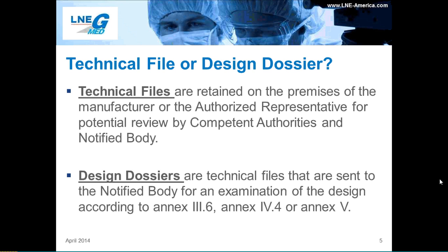At GMED, we review these as part of your on-site audit, unless there are major changes, of course, which require a review between on-site audits. Design dossiers are technical files that are sent to the notified body for an examination of the design according to Annex 3.6, Annex 4.4, or Annex 5. Keep in mind that manufacturers must maintain technical documentation for all medical devices, regardless of the device class.